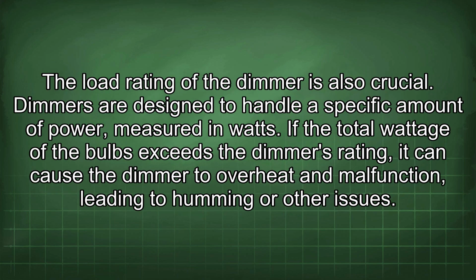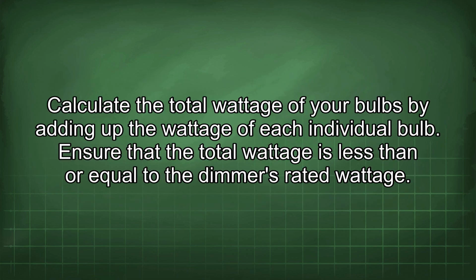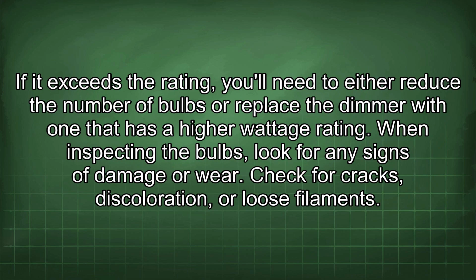The load rating of the dimmer is also crucial. Dimmers are designed to handle a specific amount of power, measured in watts. If the total wattage of the bulbs exceeds the dimmer's rating, it can cause the dimmer to overheat and malfunction, leading to humming or other issues. Calculate the total wattage of your bulbs by adding up the wattage of each individual bulb. Ensure that the total wattage is less than or equal to the dimmer's rated wattage. If it exceeds the rating, you'll need to either reduce the number of bulbs or replace the dimmer with one that has a higher wattage rating.